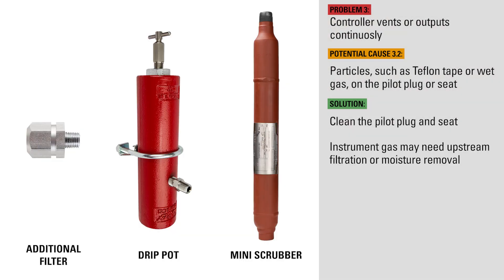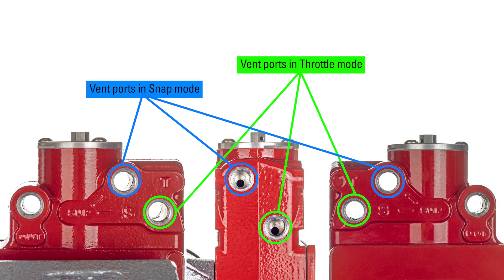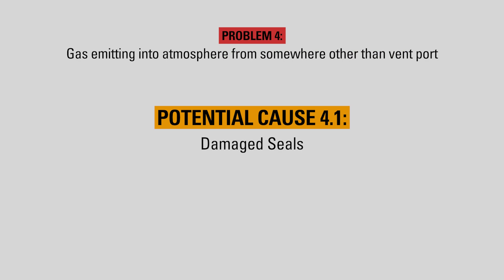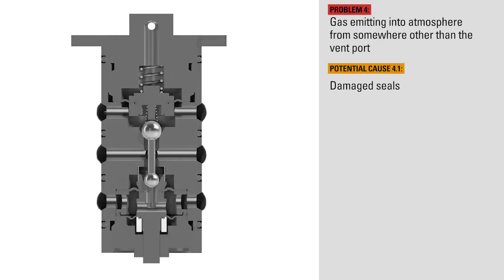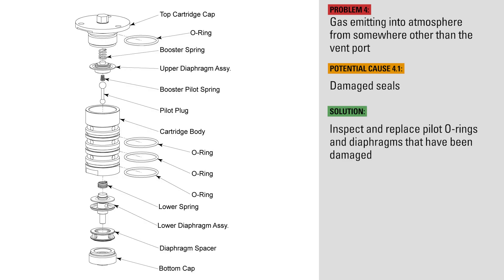In the Gen 3, the only gas that should ever be emitting is through the vent port if it's set up to vent to atmosphere, or no emissions at all if you have it set up to capture vent gas. If your Gen 3 is emitting gas from somewhere other than the vent port, like out of the bottom of the pilot or out the breather hole in the top of the pilot, it's likely an indication that the o-rings or diaphragms in the pilot have been damaged. Inspect the pilot o-rings and diaphragms and replace if necessary.